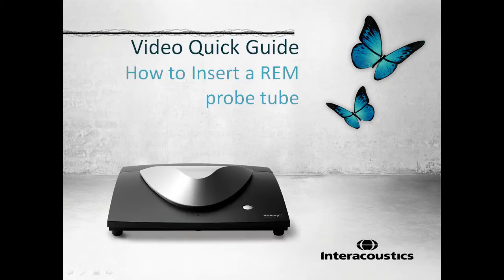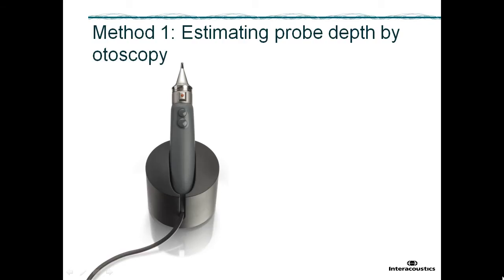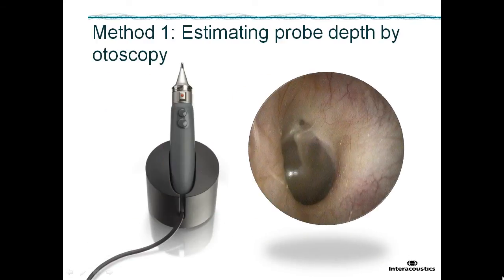Method 1. Estimating probe depth by otoscopy. In order for a probe tube to be inserted correctly, it should be placed between 3 and 5 mm from the eardrum. By performing otoscopy, one can estimate how long the ear canal is and take this into consideration when determining how deep the probe tube should be fitted.